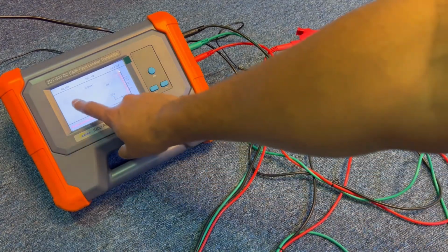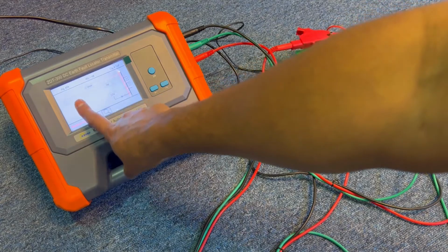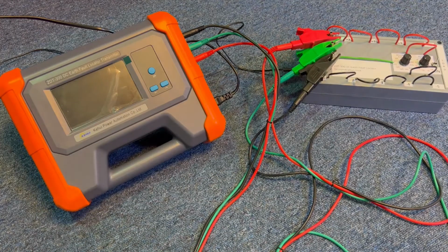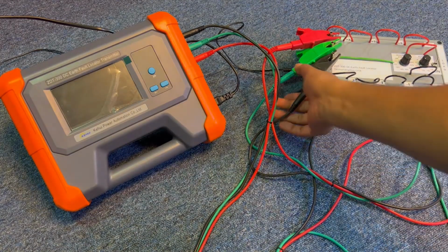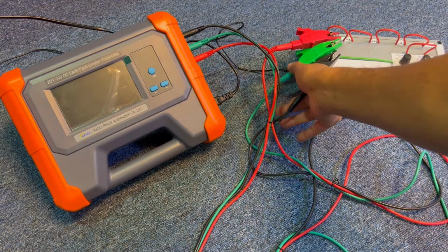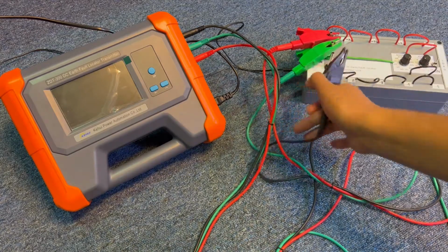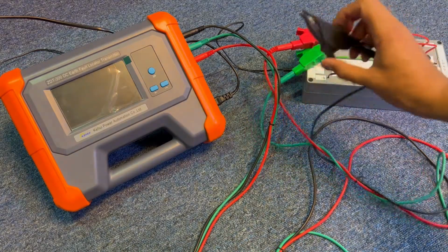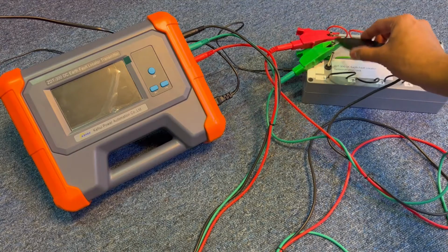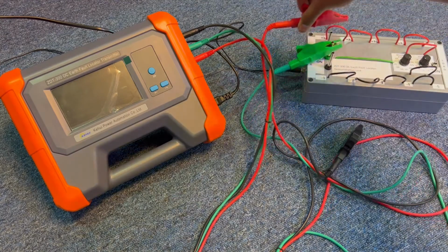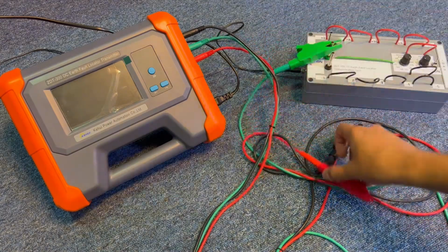One more thing we need to say, that whenever you switch off the system, we need to make sure that there is no signal injection in the transmitter. Okay, and then switch off. Always remove the connections first without removing the ground, and always try to touch this to the ground so that there is no induction in the equipment.